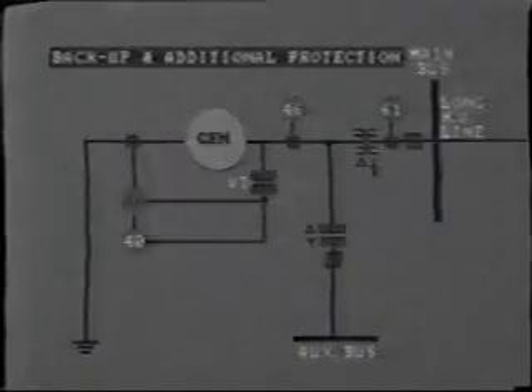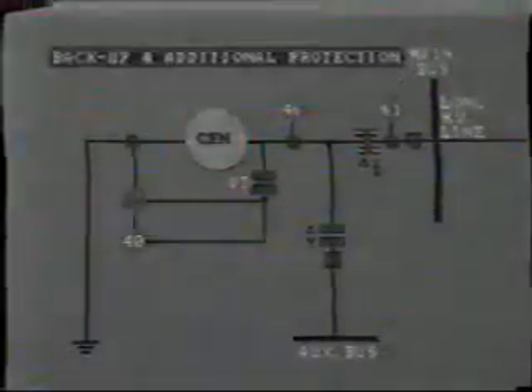As this is a backup relay, a timer is included so as to allow coordination with the other relays. The distance relay is fed from VTs on the generator's main terminals and CTs at the neutral end. The distance relay is set to operate at 150 to 200% of generator rated current. Remember, this is an impedance relay. As the terminal voltage falls, so the current trip point will also fall.